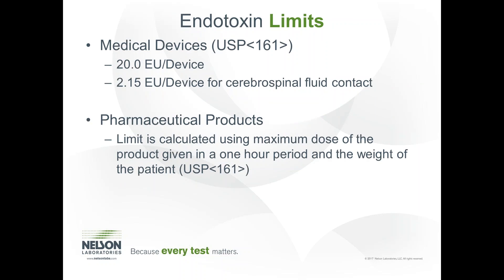Typical endotoxin limits are not more than 20 EUs per device. If the device has blood or tissue contact, and if there is contact with cerebral spinal fluid, the limits are 2.15 EUs per device. For pharmaceutical products, the limit is calculated based off the maximum dose that can be given in a one-hour time period and a standard patient weight of 70 kilograms.